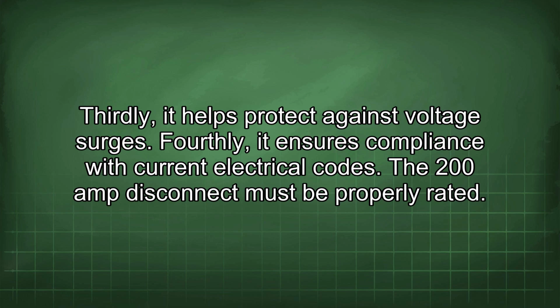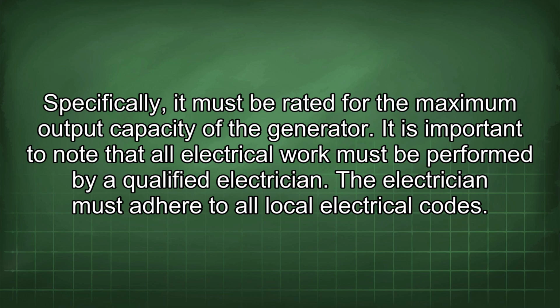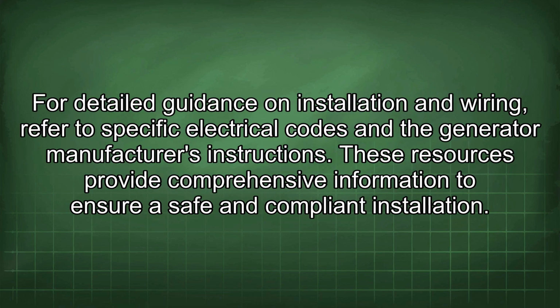The 200 amp disconnect must be properly rated. Specifically, it must be rated for the maximum output capacity of the generator. It is important to note that all electrical work must be performed by a qualified electrician. The electrician must adhere to all local electrical codes. For detailed guidance on installation and wiring, refer to specific electrical codes and the generator manufacturer's instructions. These resources provide comprehensive information to ensure a safe and compliant installation.